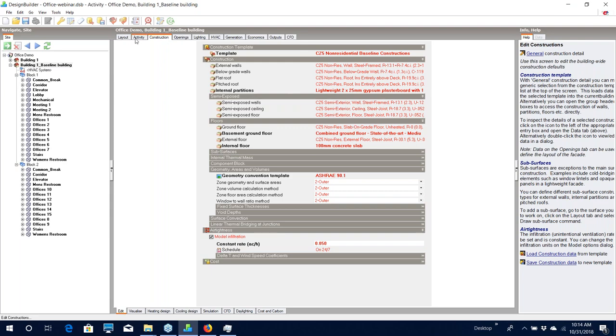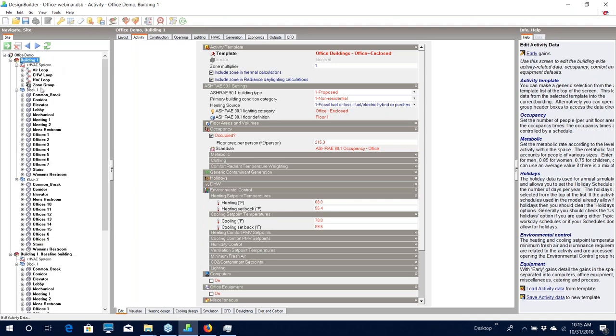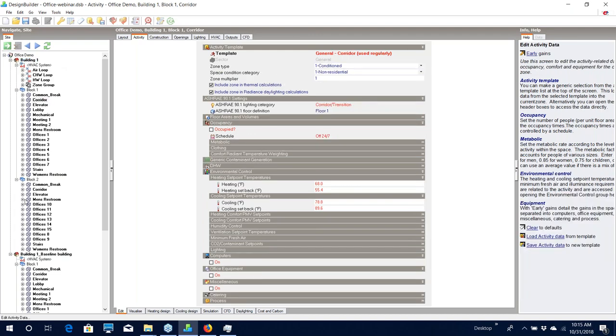If we look at the Activity tab, you can see that the activity template has not changed between the two buildings, because ASHRAE 90.1 requires these inputs to be the same between your proposed and baseline building. This is true even if we look at one of the zones where we've overridden the default template with a different choice — it is still the same between the baseline and the proposed.